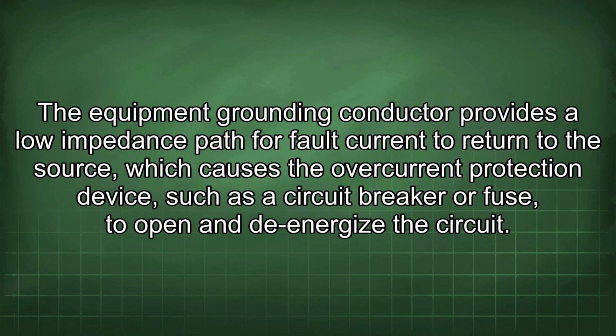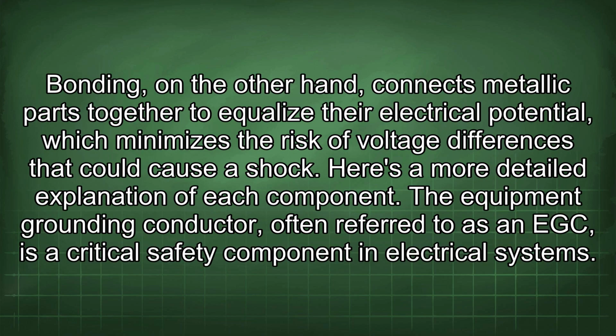The equipment grounding conductor provides a low impedance path for fault current to return to the source, which causes the overcurrent protection device, such as a circuit breaker or fuse, to open and de-energize the circuit. Bonding, on the other hand, connects metallic parts together to equalize their electrical potential, which minimizes the risk of voltage differences that could cause a shock. Here's a more detailed explanation of each component.